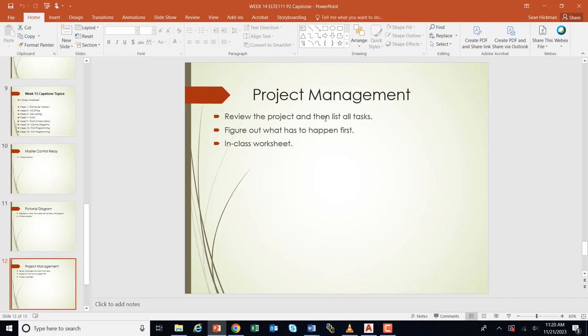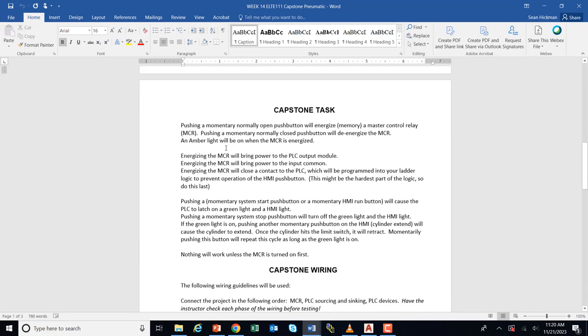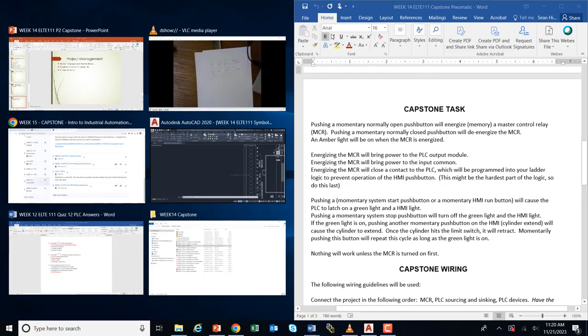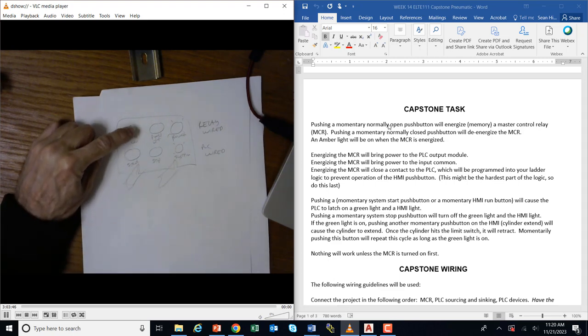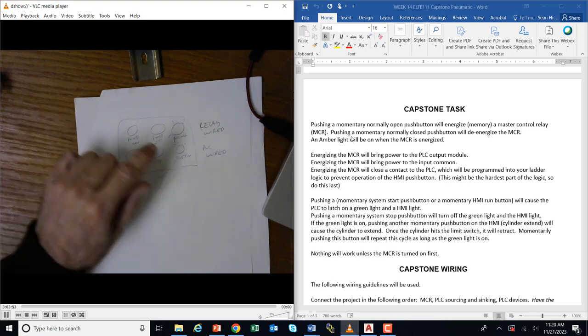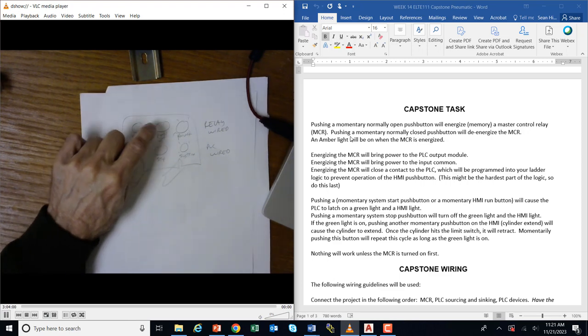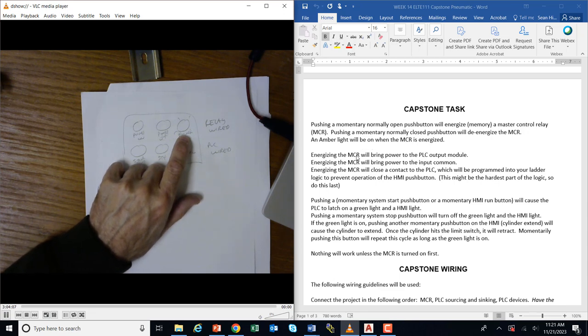For project management, review the project and list all tasks. The project description: pushing a momentary normally open push button will energize the relay — the power button is pushed momentarily, it has memory, the master control relay comes on, and a light comes on. Hit stop: everything goes off. Energizing the master control relay brings on the PLC inputs and outputs via those MCR contacts — contacts 5 and 6 turn on the voltage to the PLC. An amber light indicates the MCR is energized.